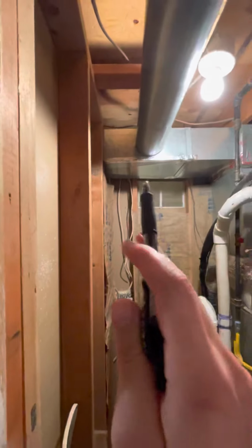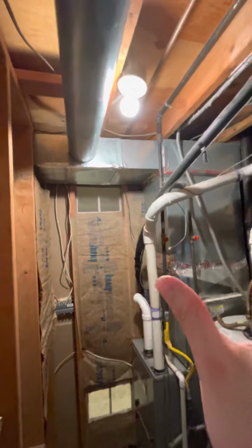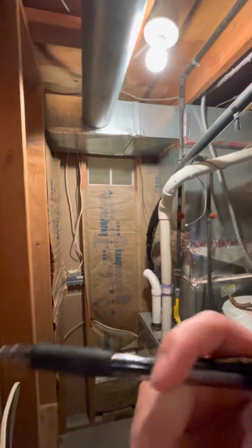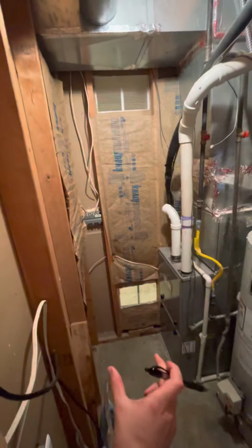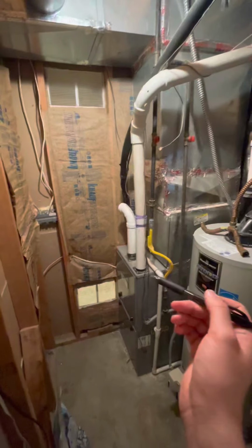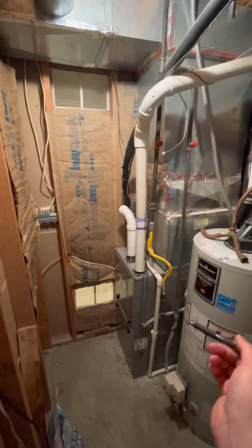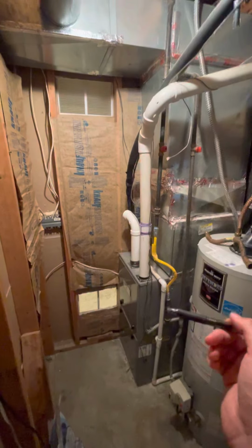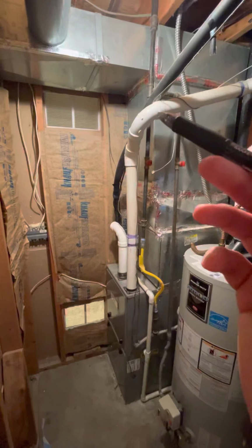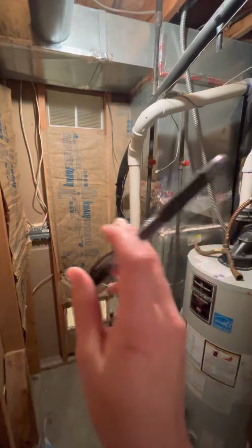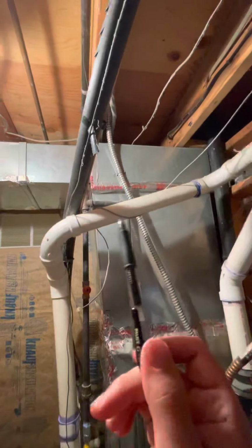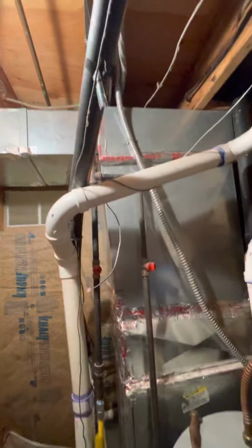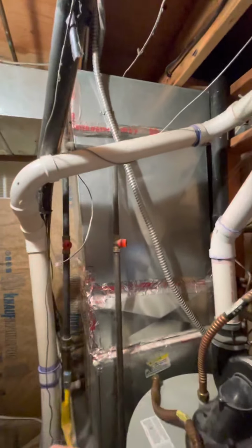You might need to make this quite a bit bigger too and make this more of a run, because you can see that's way bigger to match the plenum versus this branch line right here that we have coming off the main supply and trunk line. So that's kind of the idea. So furnace, AC coil, base can, everything right here, filter rack, and then to the right, if you guys can imagine, a cold air return, probably another base can, quite a bit of ductwork, and then a 10 by 20 running all the way up as high as we can, right about to this point, and then we need to basically fish it over, go up, and then this will be where we run a cold air return duct over, and the thermostat's right up above that, which will be perfect to add a cold air return into. This is an older house, 1978.